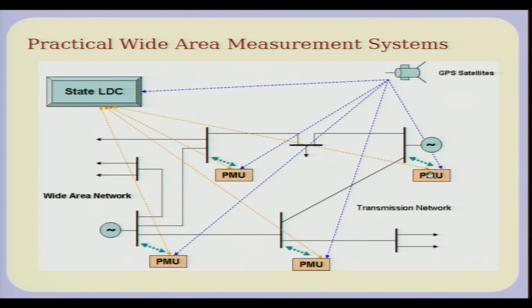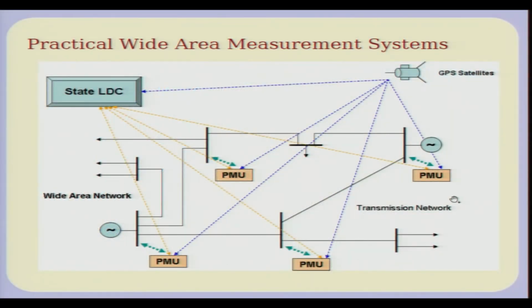Since all these phasor measurement units, which use DFT to compute the magnitudes and angles of the fundamental component of the sinusoidal waveforms, are time synchronized, you can actually compare the phasors. Since you have synchronization accuracy of a microsecond or less, your phase angle can also be compared - because without time synchronization, the phase angle of a phasor does not make sense. You should have a common time axis, and only then can we talk of phase angular differences.